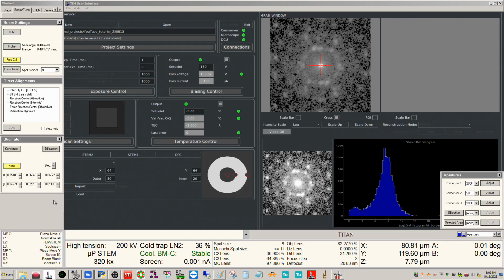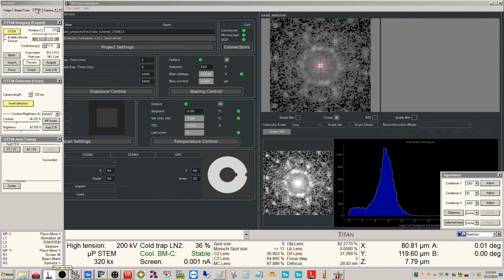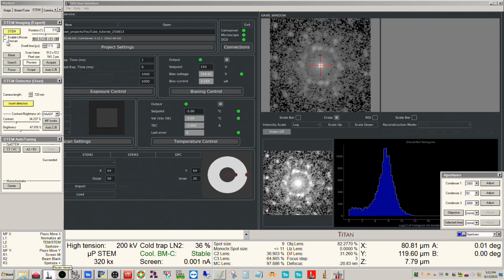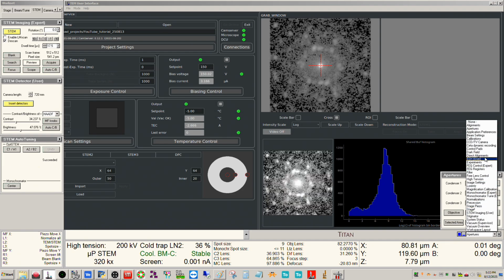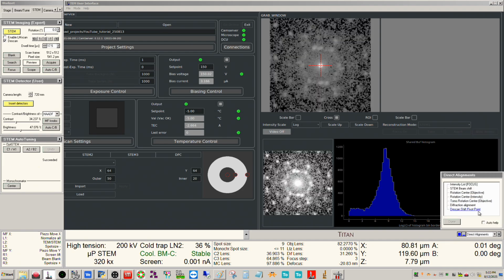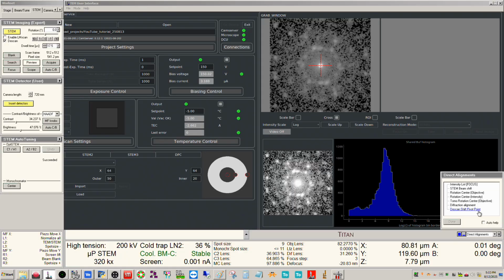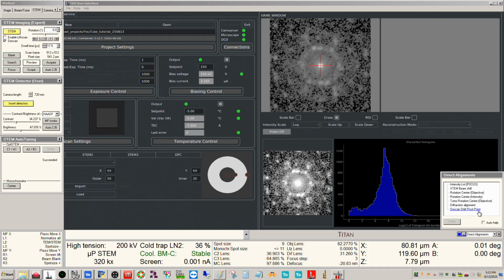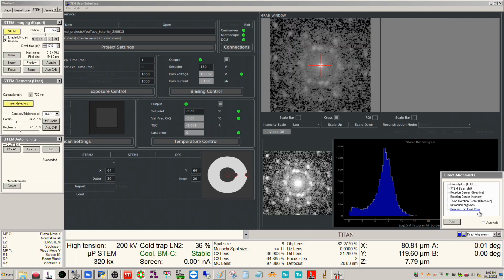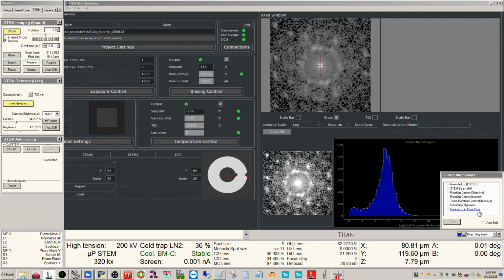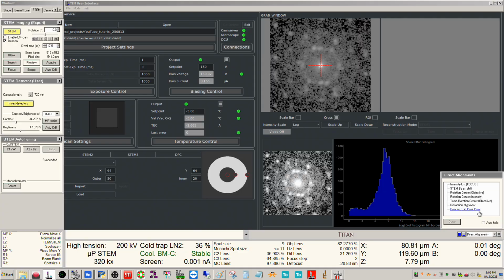And so, again, just briefly back to the descan artifact. If you check this descan here, there are direct alignments you can use to align this in theory or in principle. The problem is we've had a lot of issues with this not working properly, or being able to actually correct this well. This is something that we've had a lot of headaches with on this system.